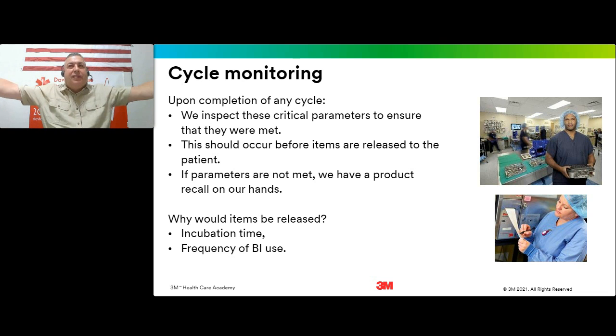But it takes a half hour to get into the incubator - sometimes they sit on the sterilizer cart. So we're defeating the purpose there. We want to get those in promptly. It's a balance between not getting it in there too fast - you've got to look at the IFU because you don't want the ampule to explode, but you also don't want it to sit on the cart for 45 minutes. So we want to take a look at that.